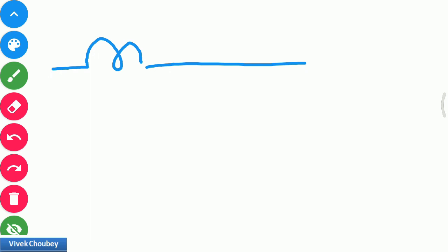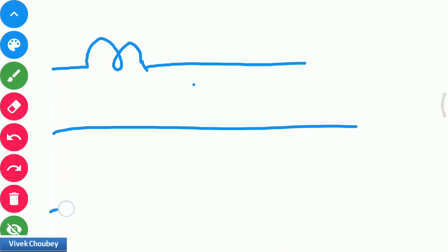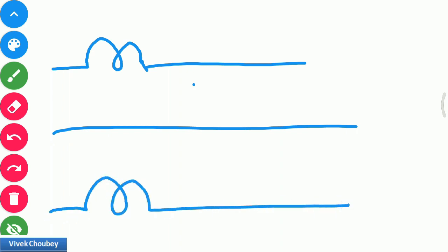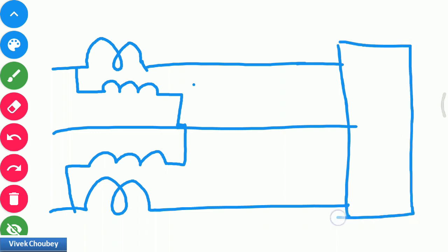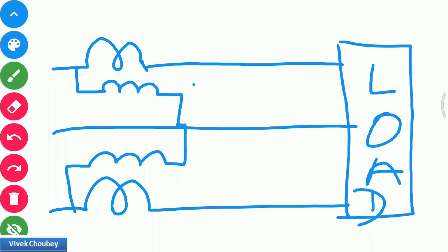A wattmeter has two coils: a current coil and a potential coil. The current coil is connected in series. Let's say this is the common phase and this is another phase. We connect the current coil in series while the potential coil is connected across the phases. This is the potential coil. This line goes to the three-phase load. This is how we connect two wattmeters for measuring three-phase power, and the power we get is √3·VI cos φ — that is the active power.